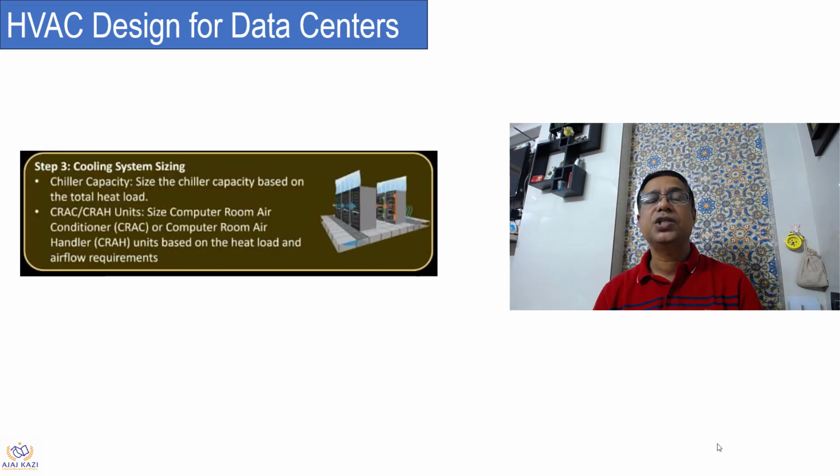The second aspect is cooling system sizing. You need to be very clear about the chiller capacity. The major issue when you select the chiller is if there is a power outage, the chiller has to come to work on DG. There should not be a major gap, so the quick restart is important. The maintenance of the chilled water temperature, because we're talking about higher chilled water temperature here, is important. So you need to be able to size the chillers.